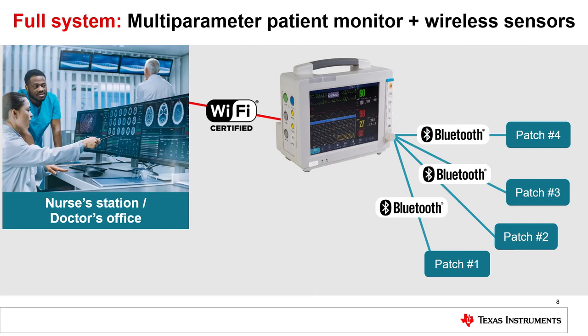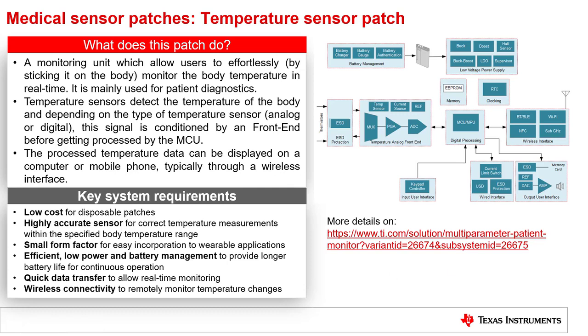Let's have a look at some of the sensor patches. A temperature sensor patch is a monitoring unit which allows users to effortlessly monitor the body temperature in real time, mainly used for patient diagnostics. Temperature sensors detect the body temperature and, depending on the type — analog or digital — the signal is conditioned by an analog front end before being processed by the MCU. The processed temperature data can be displayed on a computer or mobile phone, typically through a wireless interface.